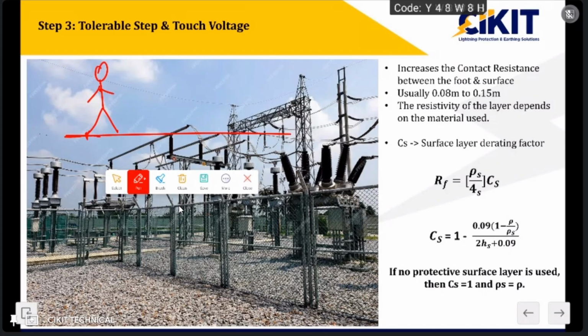So in this case, here he is making direct contact with the soil. So if the ground potential is increasing, the potential between the 2 feet will also increase. In order to avoid that, we provide a high resistance layer. If this high resistance layer is there, the person will be standing on it. Because of the resistance of this layer, even though the soil potential is increasing, the same voltage won't be reflected on top of this high resistance layer.